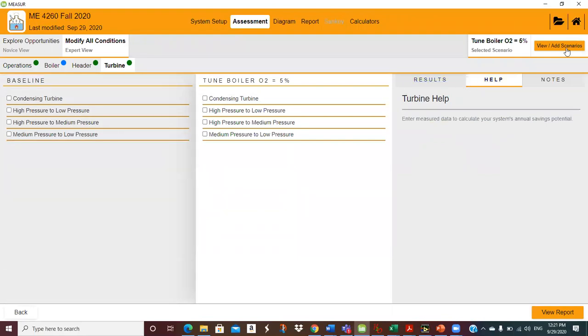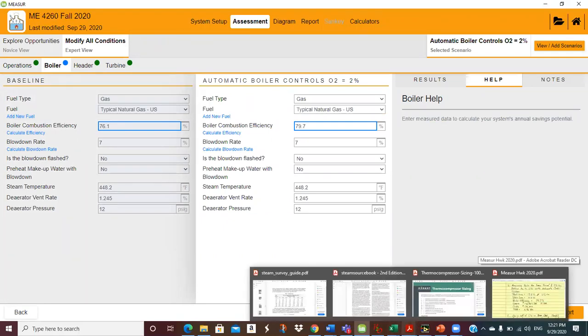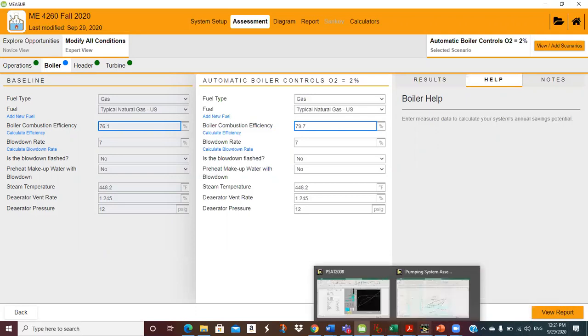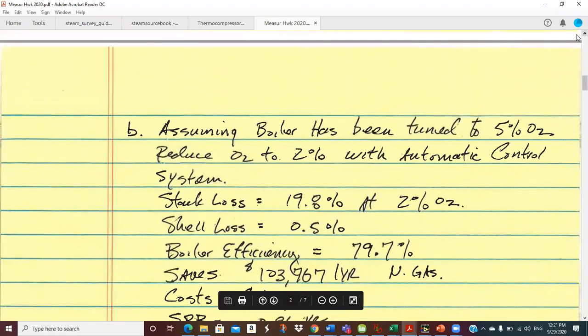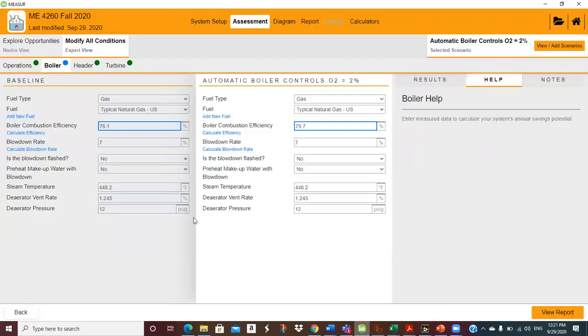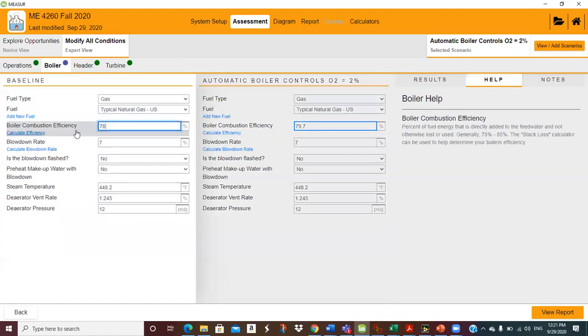Let's go to the scenario — this is the 2% O2 case. You've got to be careful when you start changing this stuff, because that 76.1% is the 8.1% oxygen base case. That's not right — that's going to give me too much savings. I've got to go back up to the 5% case and get 78.3. That's what I was thinking, but I wanted to be sure.